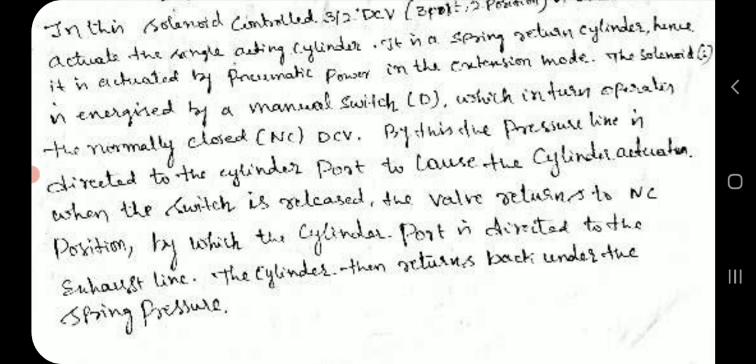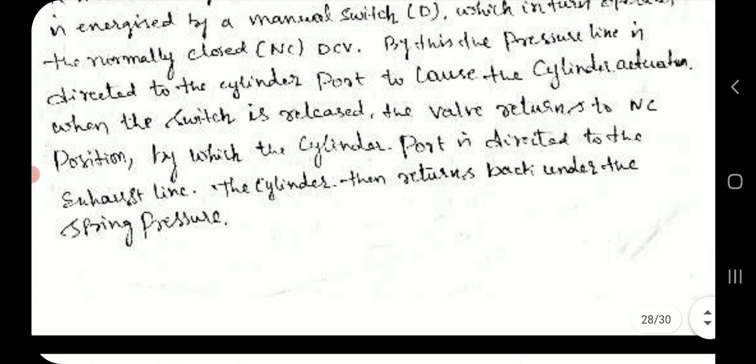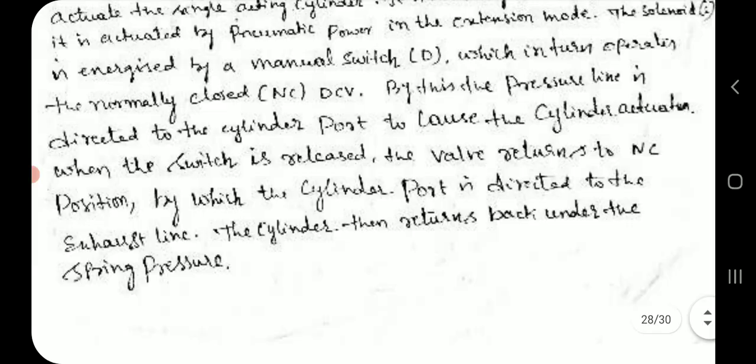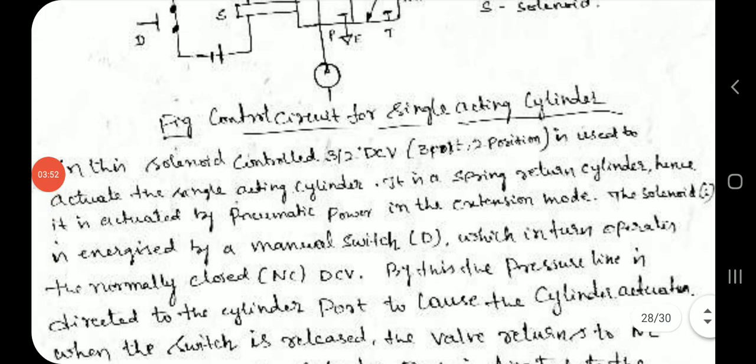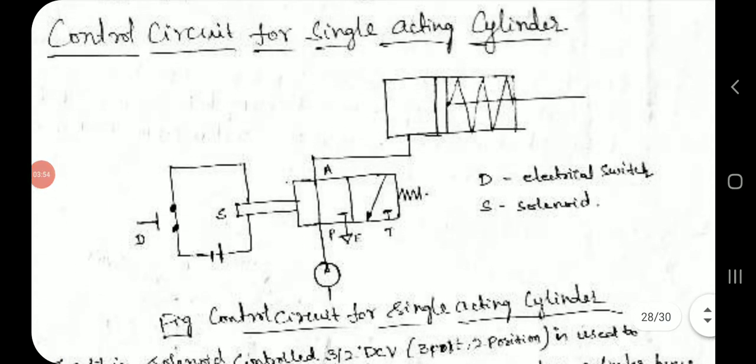When the switch is released, the valve returns to the normally closed position, by which the cylinder port is directed to the exhaust line. The cylinder then returns back under the spring pressure. This is the diagram of the control circuit for a single-acting cylinder, showing the electric switch D and solenoid.